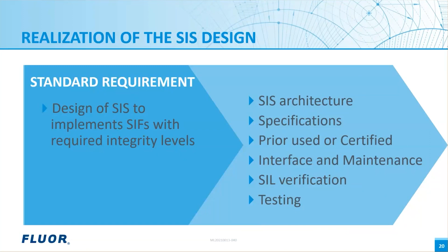When we do the hazard and risk analysis, we know what is required for safeguarding the process. For simpler processes where reactions are slow, and even if a hazardous event occurs the risk is not great, where there's no harm to people or the environment and no damage to equipment, then you don't require safety functions or safety instrumented systems.